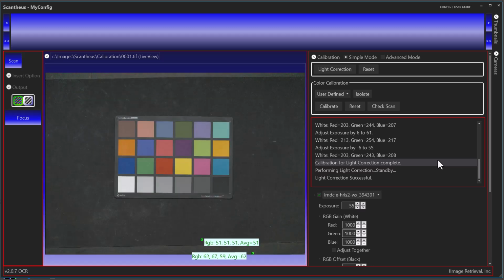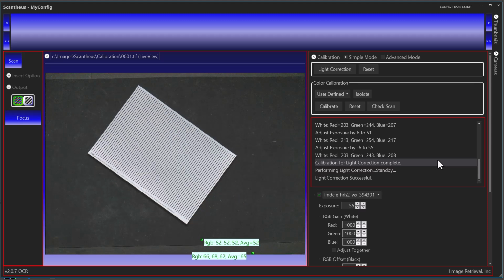We're going to do a focus that you can actually run at any time, but it's kind of like light correction. You don't need to run it very often unless you see, in this case, your images seem to get a little blurry. That's what this button is over on the left. You see a focus button, and I'm going to use a sheet that comes with the scanner, the line sheet. And the important thing is that when you're scanning, you press your material against the glass, because that's where your focus distance is going to be.